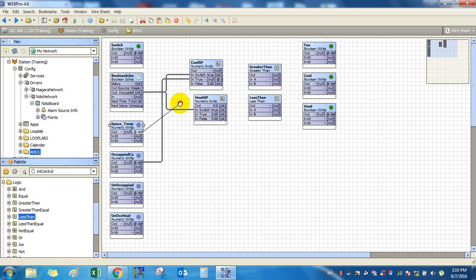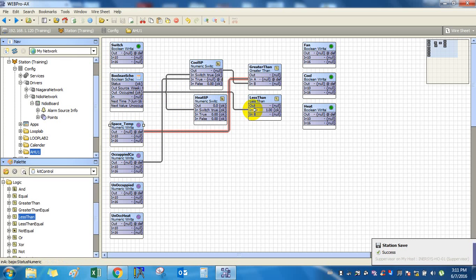So the out of this will go to your cooling command. Similarly, when your space temperature is less than your heating set point, that is, your space is too cold, at that time you will need heating in your space. So link the out of this less than block to your heating command.